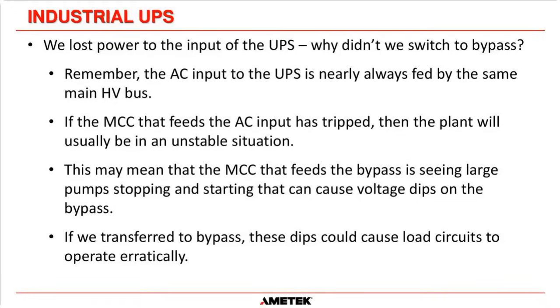So that may mean that the bypass, if you switch to bypass, which is fed from somewhere else in the plant but using the same HV power supply, there may be large pumps stopping and starting and things going all over the place that can cause voltage dips onto the bypass. So if we transfer to bypass, those dips would be seen by the load circuits, and it could mean that the load circuits would operate erratically.